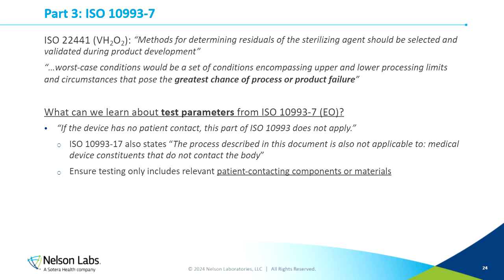So this is where communicating with the lab and making sure that everyone's on the same page with exactly how your device is used and what surfaces have relevant patient contact can help you out to not have an overestimation of patient exposure in a completely irrelevant way. We want a worst case exposure to be measured, but we still want it to be relevant.